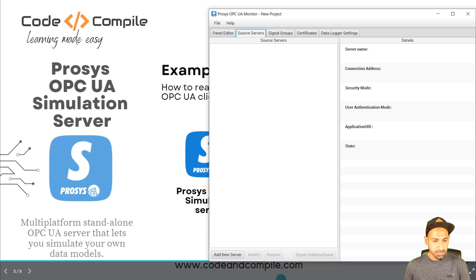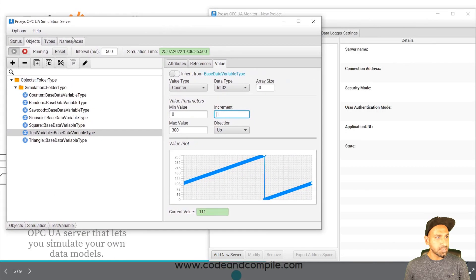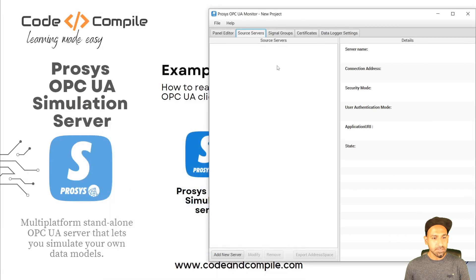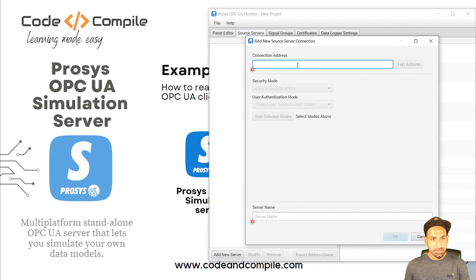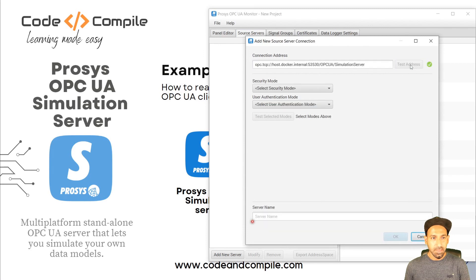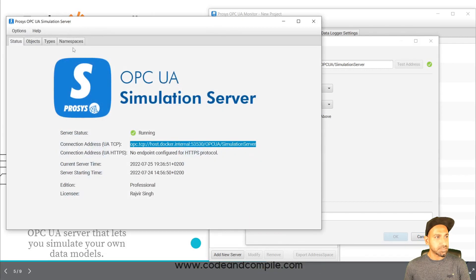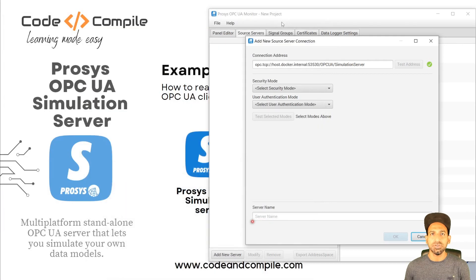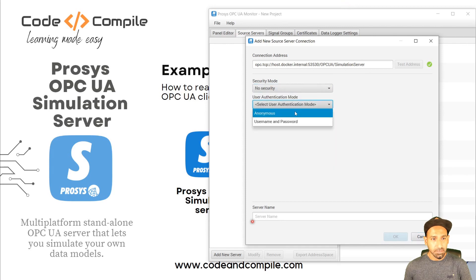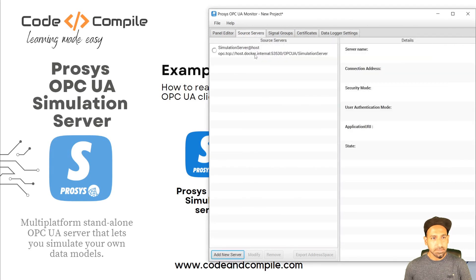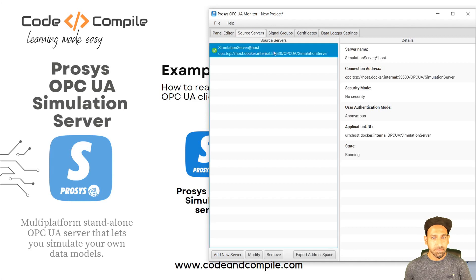To add the server, you need some server details. Open the Prosys OPC UA Simulation Server, go to Status, and find the address. Copy that address, add a new server, paste the address, and click Test. Based on your security mode — at the moment anonymous is enabled in this OPC UA server — I'll log in as anonymous. You can also set a username/password or certificates, but for testing, anonymous works fine. Click OK. Your server will connect, and in a fraction of seconds you'll see it's connected.